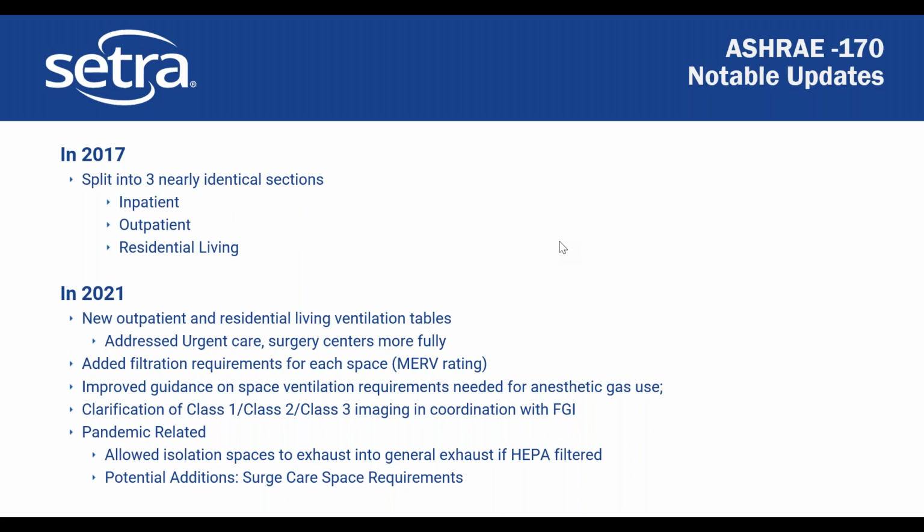Residential living facilities obviously are very, very different than a hospital. So they provided ventilation tables for that, which include a number of unique spaces like hair salons that you would almost never see in a hospital or major health center. They also added filtration requirements for each space. So now you actually have a MERV rating requirement for the filters on all of these spaces.